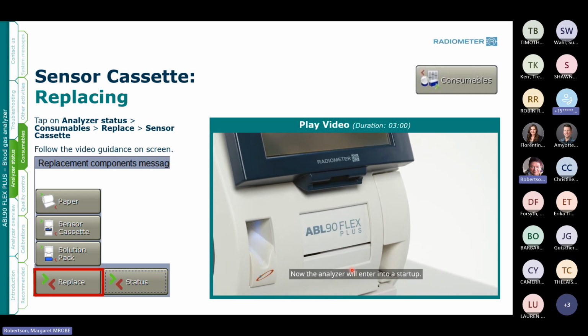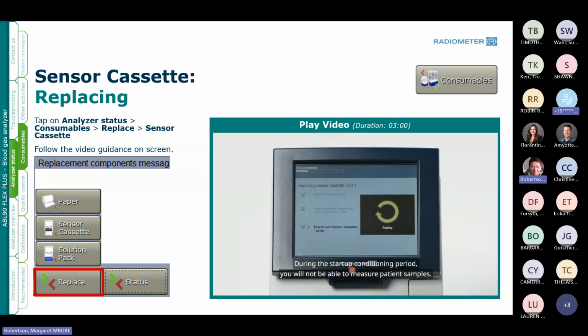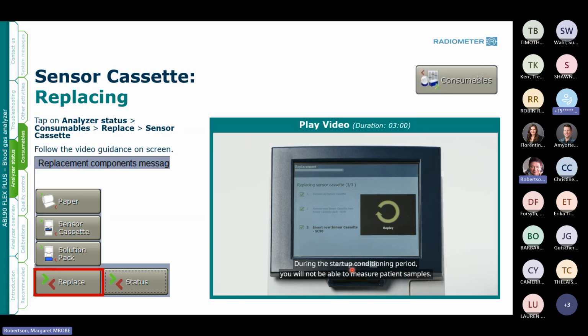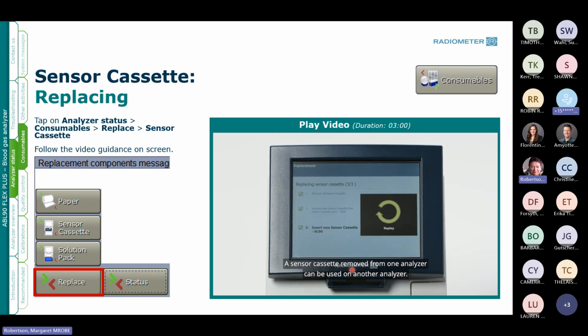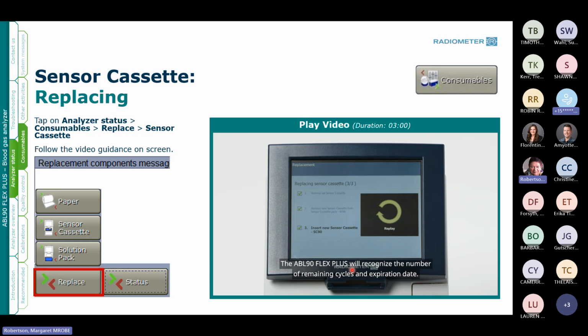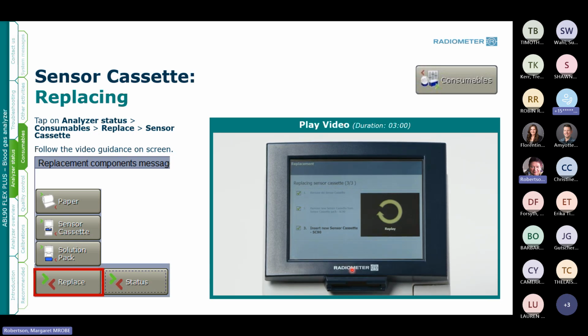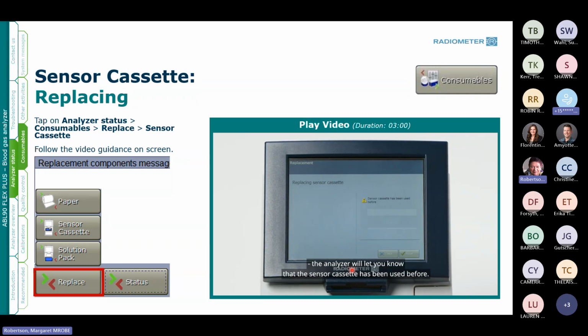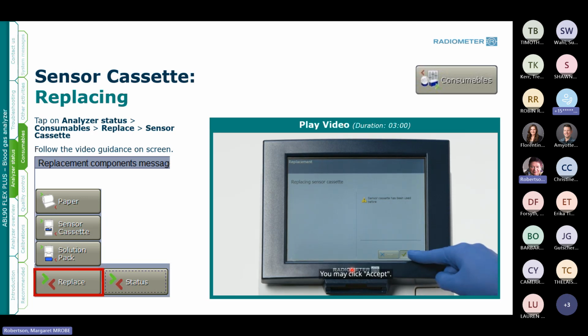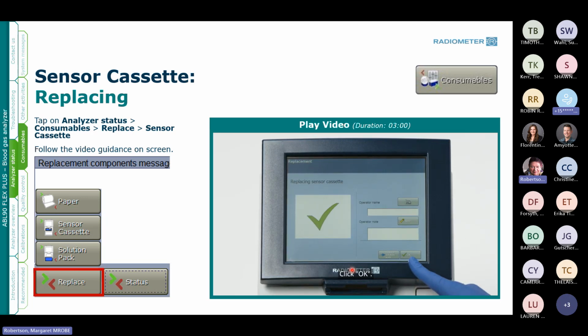Now the analyzer will enter into a startup. During the startup conditioning period, you will not be able to measure patient samples. A sensor cassette removed from one analyzer can be used on another analyzer. The ABL90 Flex Plus will recognize the number of remaining cycles and expiration date. If you install a sensor cassette that you have already used, the analyzer will let you know that the sensor cassette has been used before. You may click Accept. Click OK.